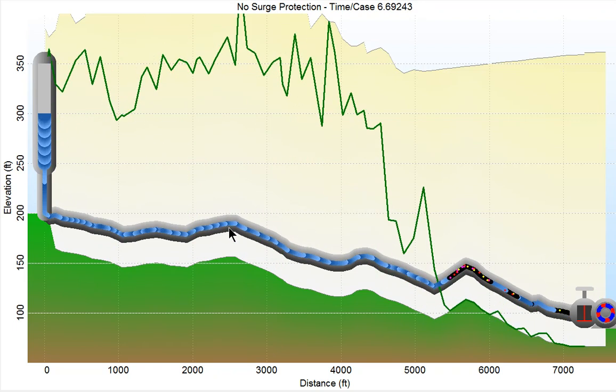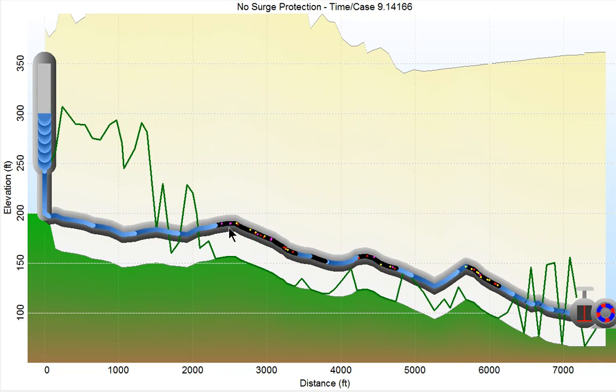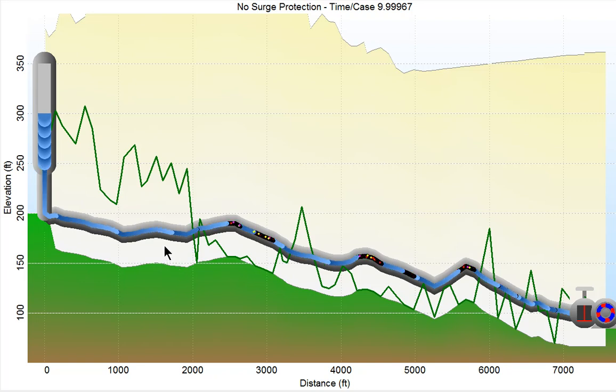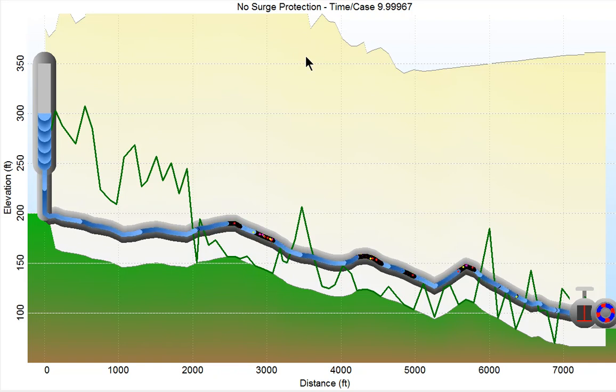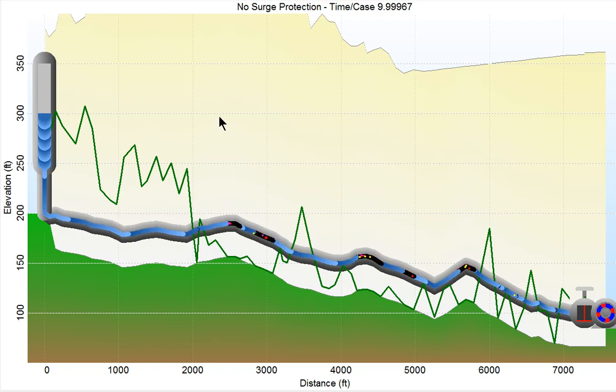We're having a very serious transient in this situation. We're running a 10-second simulation, and what you're seeing here is an envelope of the minimum and maximum pressures. The minimum pressure is at all places in the line about minus 30 feet, which is cavitation, and we have maximum pressures that are very high. This is an unprotected system, and we certainly would not want to design a pipeline and pump station that did this.